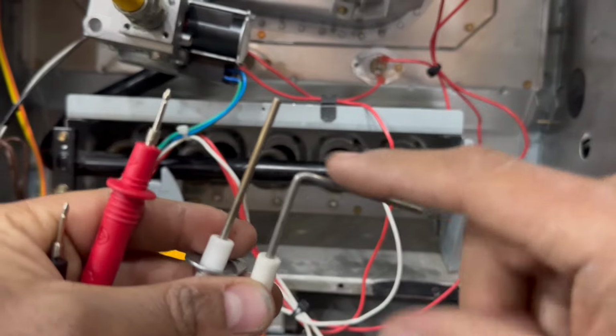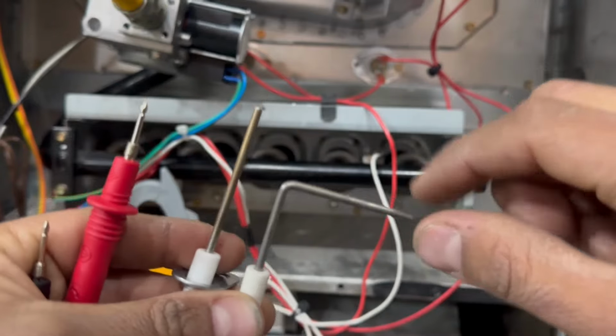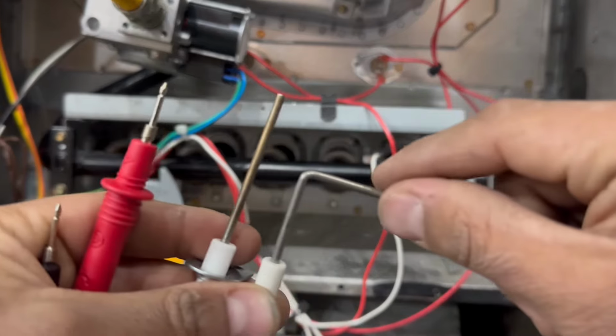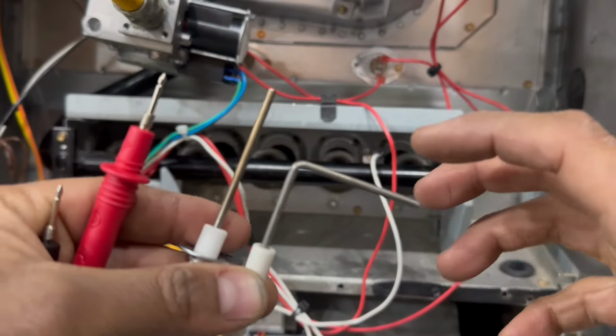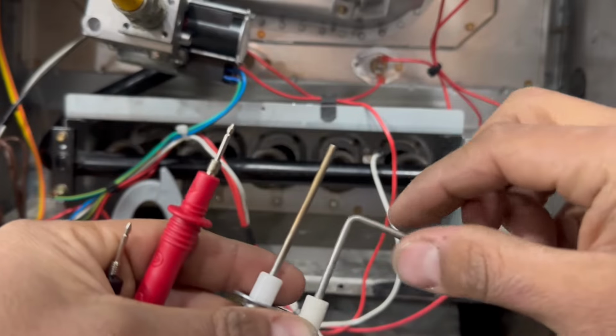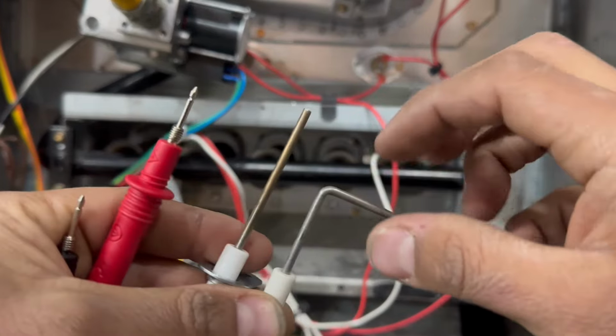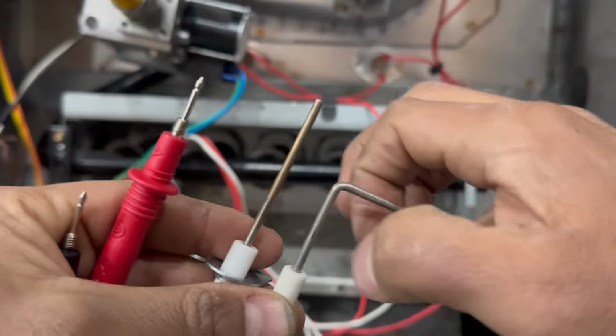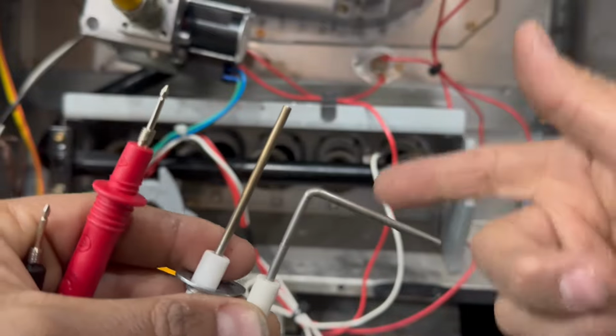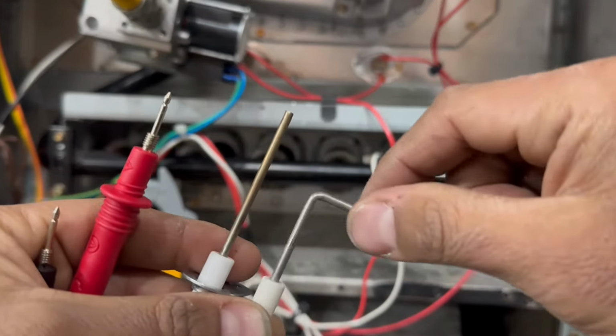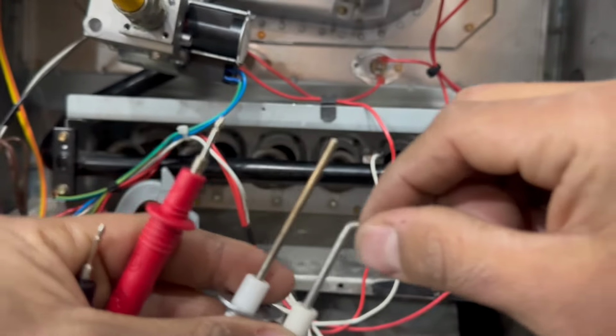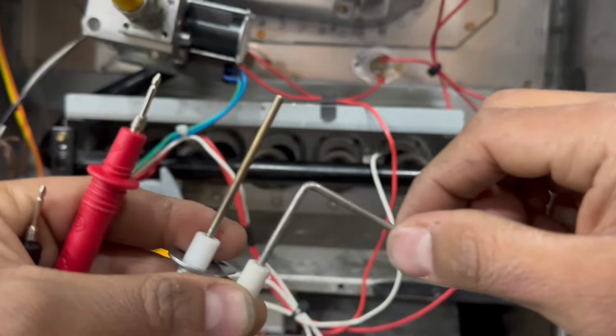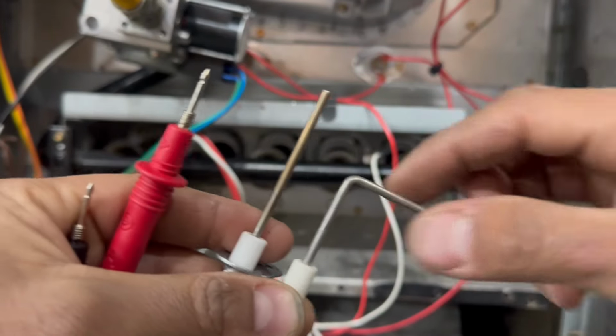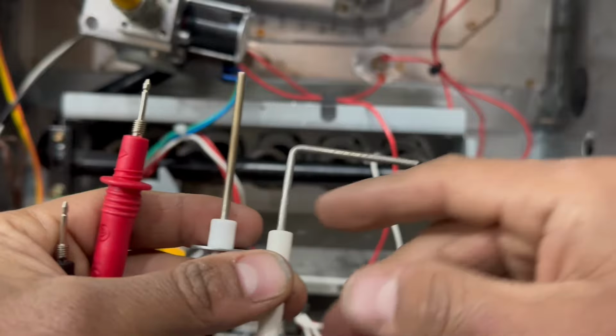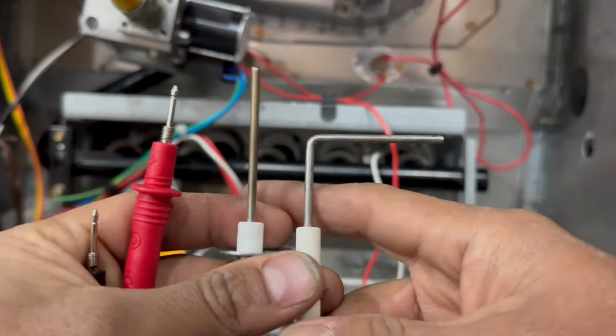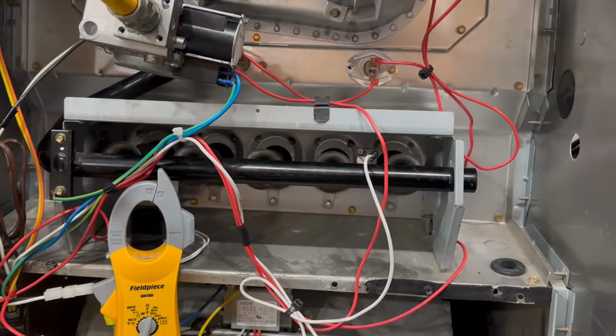You have to use steel wool to clean them. You can even use a dollar bill. You do not want to use sandpaper, because sand and heat basically create glass. So if you use sandpaper, it'll create a glass-like coating, and you won't get a proper reading, which we're going to show you right now how to check on a flame sensor. But you want to make sure you use steel wool, a dollar bill, or something that the manufacturer specifically recommends. I've always been successful with steel wool or a dollar bill. So that one, let's go ahead and check that.